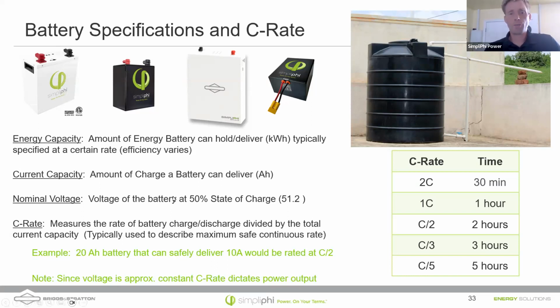Nominal voltage is the voltage of the battery. People use this word differently. Nominal voltage for us means the voltage of the battery at a 50% state of charge. For us, that's 51.2 volts for our 48 volt batteries, and half of that for the 24 volt batteries. C rate for batteries is how quickly you can charge or discharge them continuously. So the C rate on our batteries is C/2, and that's true for all of our batteries.